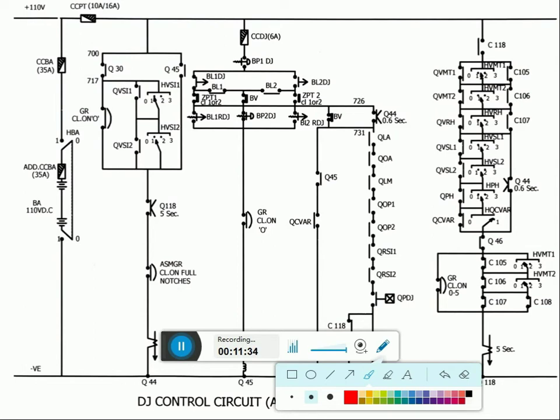This test is to be conducted in LT. In LT, we have to close DC, take the notches up to 32, keep MB on 0, and count the time. The traveling time for GR from 30 to 0 should be 11 to 13 seconds. So it will ensure proper traveling of GR. If TLC permits, after conducting the GR efficiency test, we can wedge Q44. After wedging of Q44, you have to follow precautions.